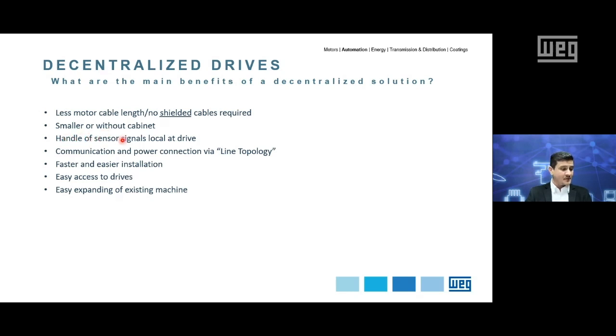Handling of the sensor signal at the local drive means less cable length for the complete machine, considering the cables are not going to the control panel. Communication and power via line topology is a cleaner and easier connection concept, also reducing the installation time and installation cost. So this is a very important note to be mentioned as well. Faster and easier installation, in case we have to do maintenance or exchange the drive if required.